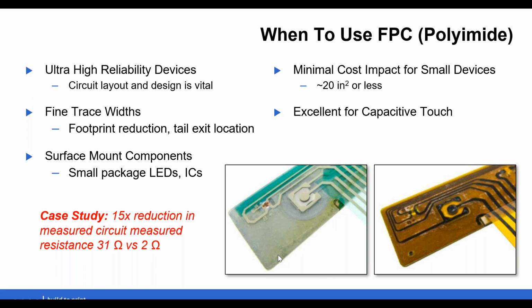There's a number of benefits as discussed, but big picture, it's a very minimal cost impact for a small device. There's a typical rule of thumb we follow where it's really 20 square inches of surface area or less. It's really more or less a cost neutral or minimal cost impact. When you get to large devices in excess of 20 or 30 square inches, that's when we see the cost impact start to really spread.